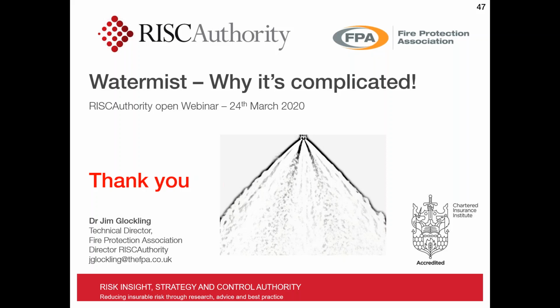Well, there is now a British standard for commercial systems, but for the reasons I suggest, we treat it with some caution for bulbed closed head systems. I think the problem that we have with development of standards is that now you can hold a sprinkler standard in one hand and a Watermist standard in the other, and assume equivalency just on the basis of the documents being in existence. But as I said, there are things in harmony with things like the FPA rules for automatic sprinkler protection. Sprinkler systems, inherent in the name, is a lot more specifically to do with area of coverage.